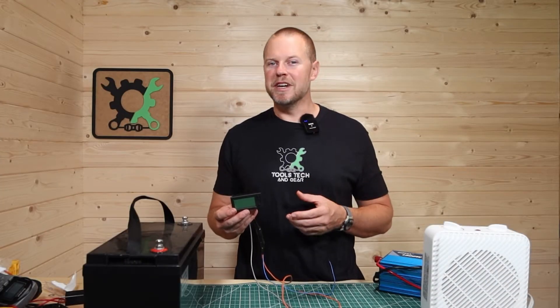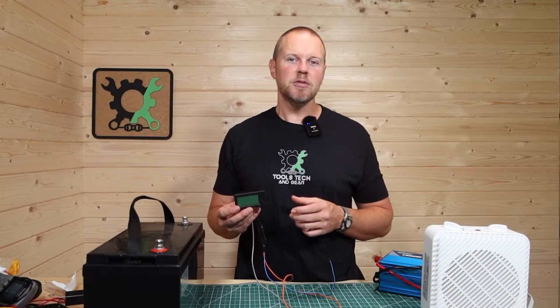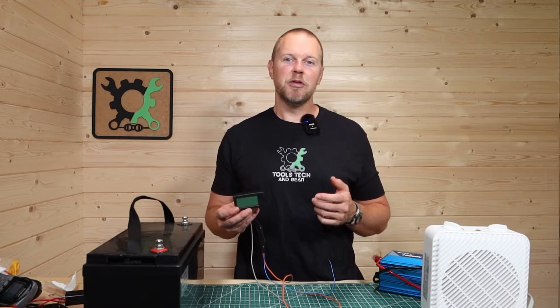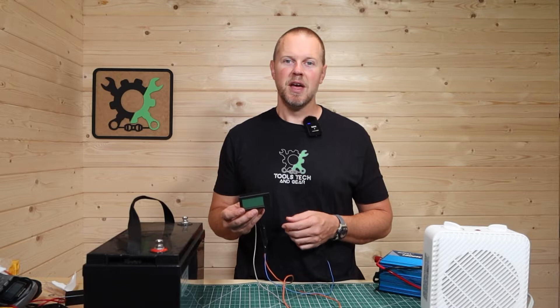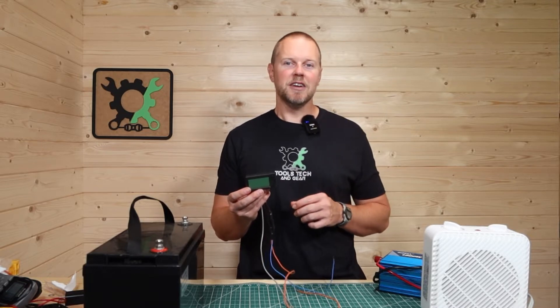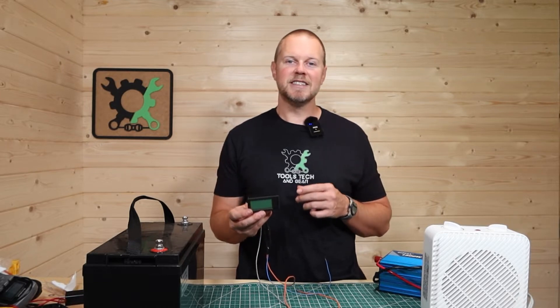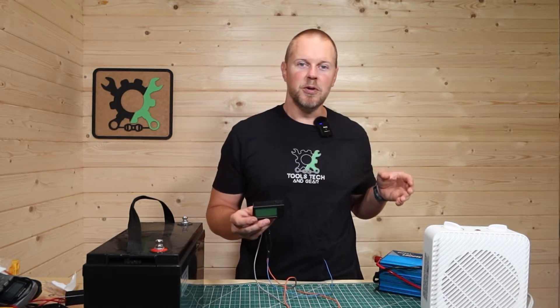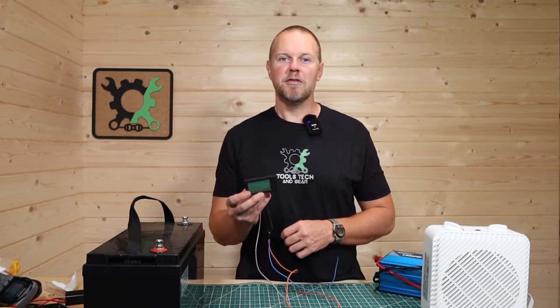Welcome to Tools, Tech, and Gear. I'm Seth. This is the DROK battery meter. Its input voltage range is 5 to 90 volts. It'll read anywhere from 0 to 300 volts, and it has an amp range up to 200 amps. The instruction book that comes with this little meter is not all that clear, so I just want to quickly go through the settings, get this set up to a battery, and show you a load being pulled from it so you can set up your own meter.